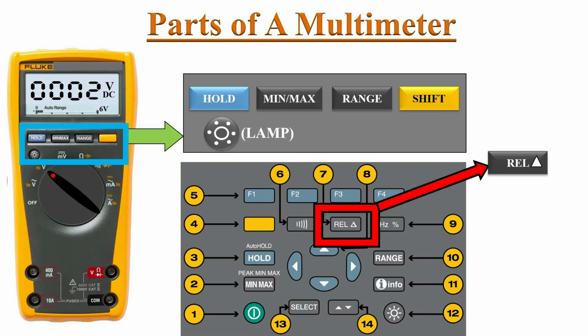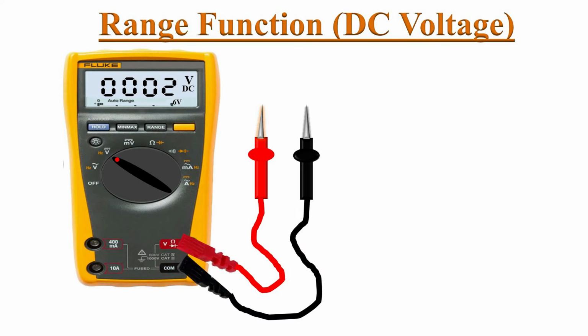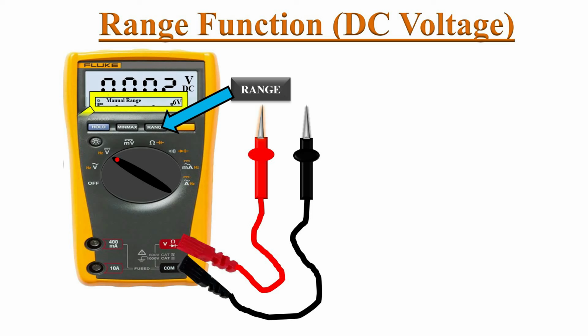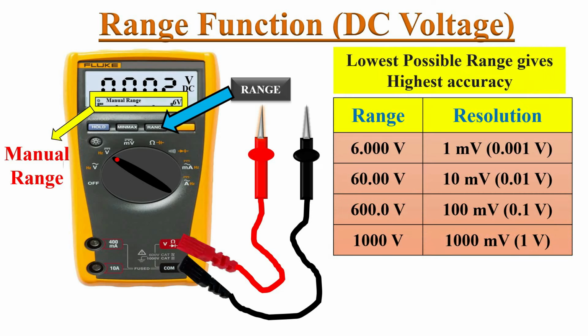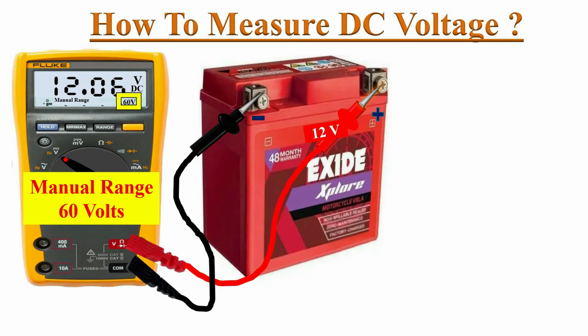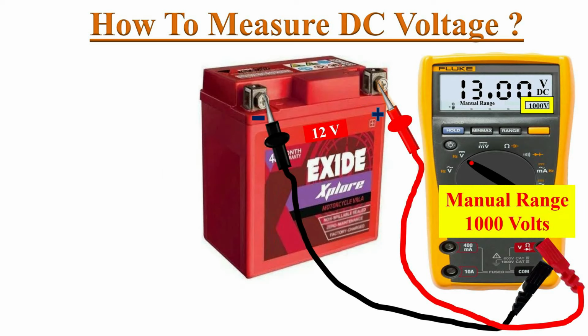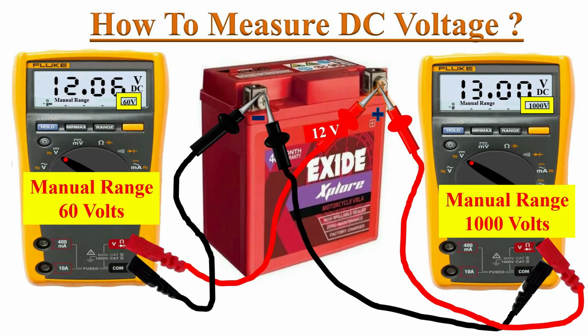Now we will discuss some key functions which help us get the best out of this measurement tool. First one, range function. If you push this button, the meter switches to manual range. By selecting the lowest possible range, we can get the most accurate measurement. For example, if we measure a 12 volts battery with the 60 volts range, then the meter reads 12.06 volts. If we change the range to 1000 volts, then the meter reads the battery voltage as 13 volts. This type of measurement error can be eliminated by setting the meter to the lowest possible range.